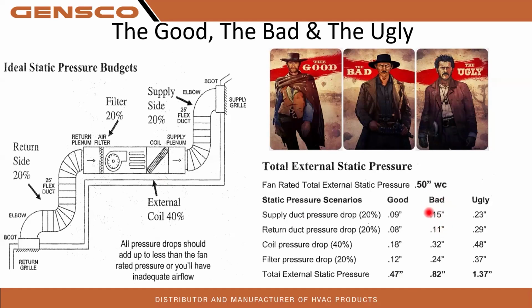When we start getting some heavier static pressures, 0.82 is bad, but it's still going to be operating. Ugly is at 1.37. When we start getting over that inch of water column, we're possibly going to start leading to premature failures and discomfort in the home. Now, premature failures are job security, but we don't want that homeowner discomfort to lead to bad reviews. All pressure drops should add up to less than the fan rated pressure, or you'll have inadequate airflow. Inadequate airflow is going to lead to discomfort, and it's going to lead to premature failure.